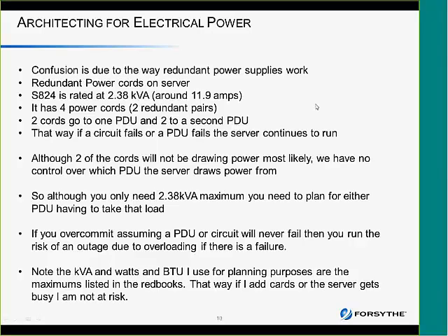So let's talk about how we architect for this, right? I've given you some of the basics. And a lot of the confusion is due to the way redundant power supplies work. Because if I tell you that my 824 is rated at 2.38 kVA, which is around 11 amps, I've got 4 power cords, 2 pair that are the live ones and 2 that are redundant. So we take 2 cords to one PDU and 2 to a second PDU. What I'm telling you is you actually have to plan as if you were going to be using twice the kVA, twice the amps.